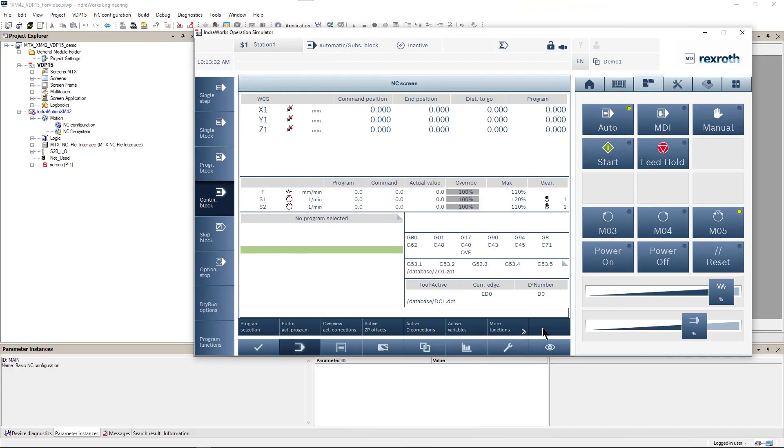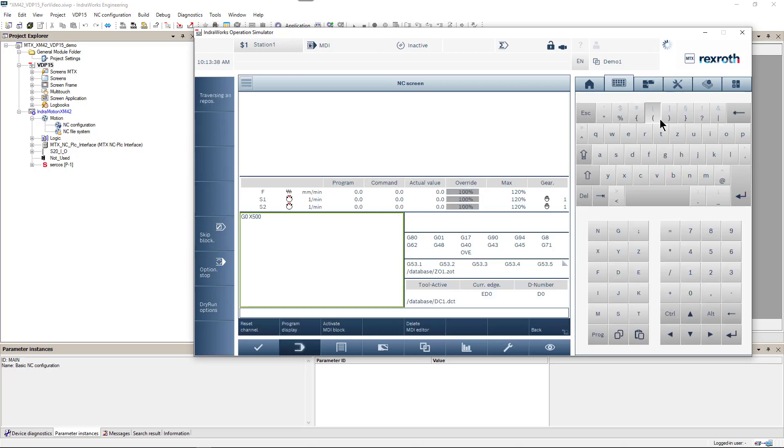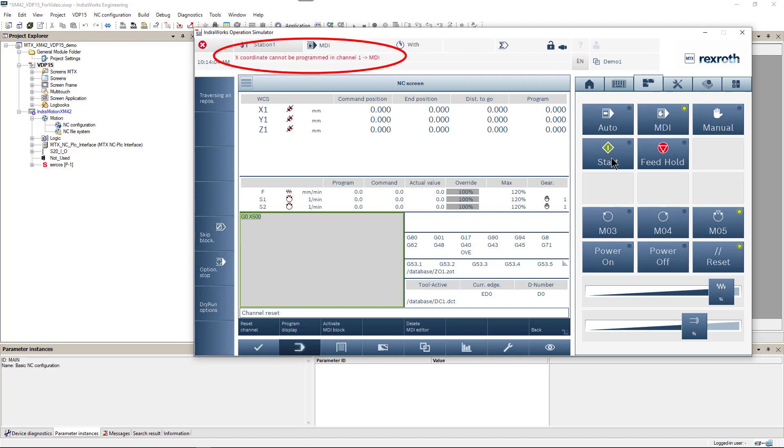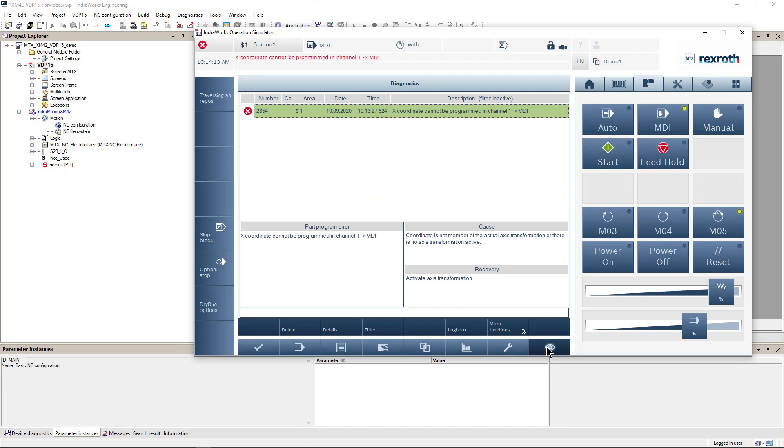Let's go back to our channel 1 and activate MDI mode. We will try to use the same motion command that worked fine before. But this time we got an error. X coordinate cannot be programmed in channel 1. We can open Diagnostics screen to get more detailed description of this error.